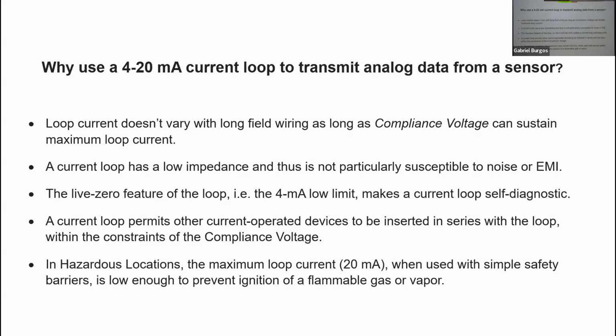Now, here's another feature which is very popular in the real world. Current loop allows you to put other current operated devices in series with the loop. So not only do you have where it's going for the controls or whatever, you also take a field milliammeter and stick it in if you want to check what's going on and so on, okay? So there's a lot of advantages to that, especially for diagnostics, you know? If you're not sure where the problem is, this is a good way to get to it.